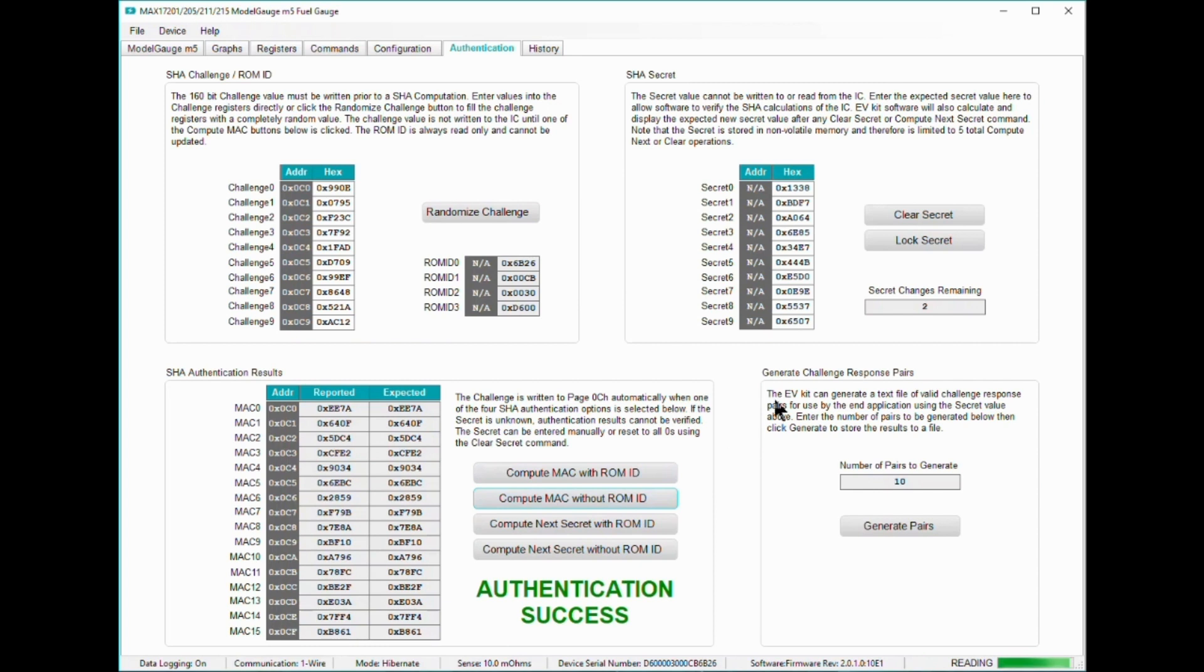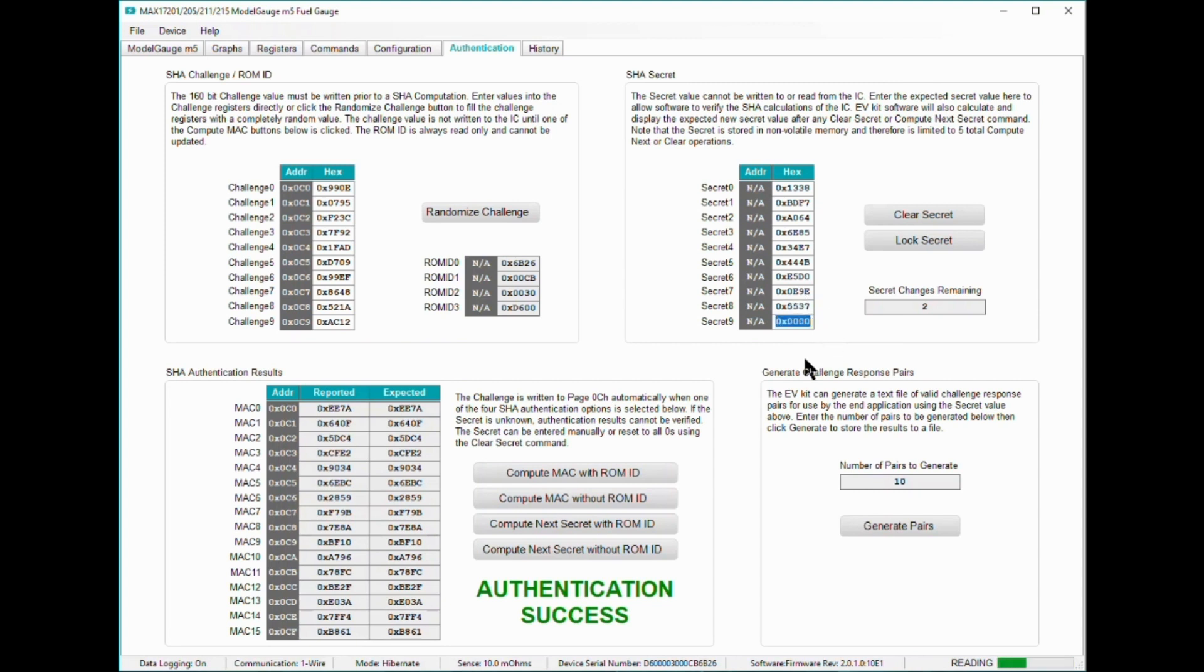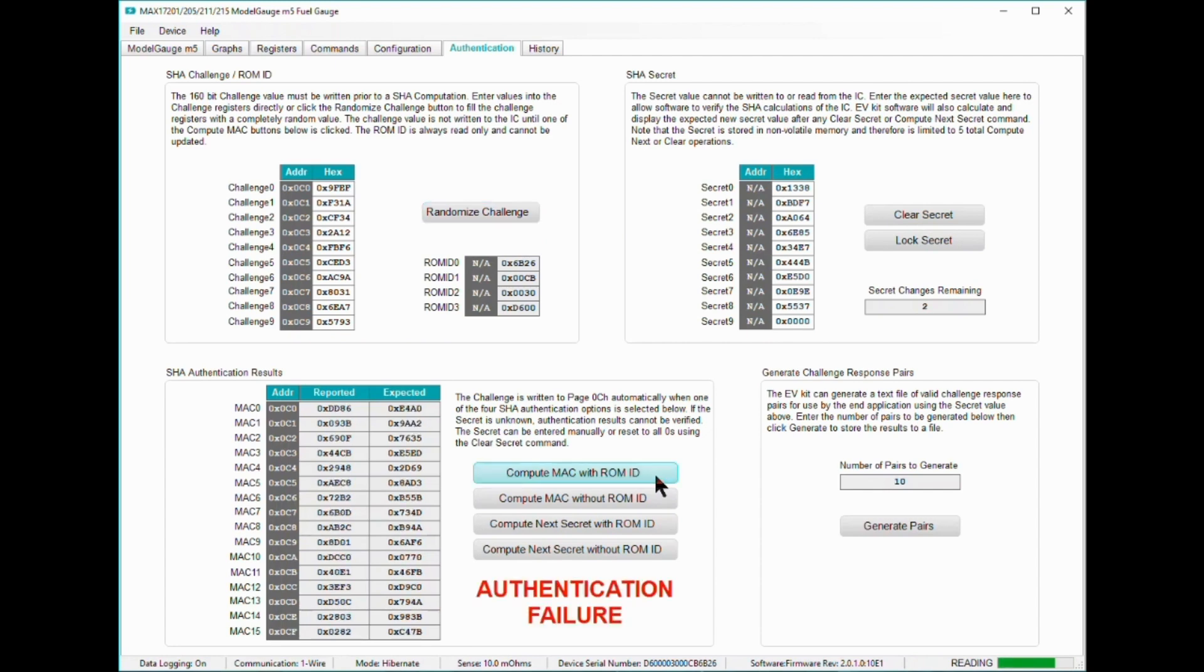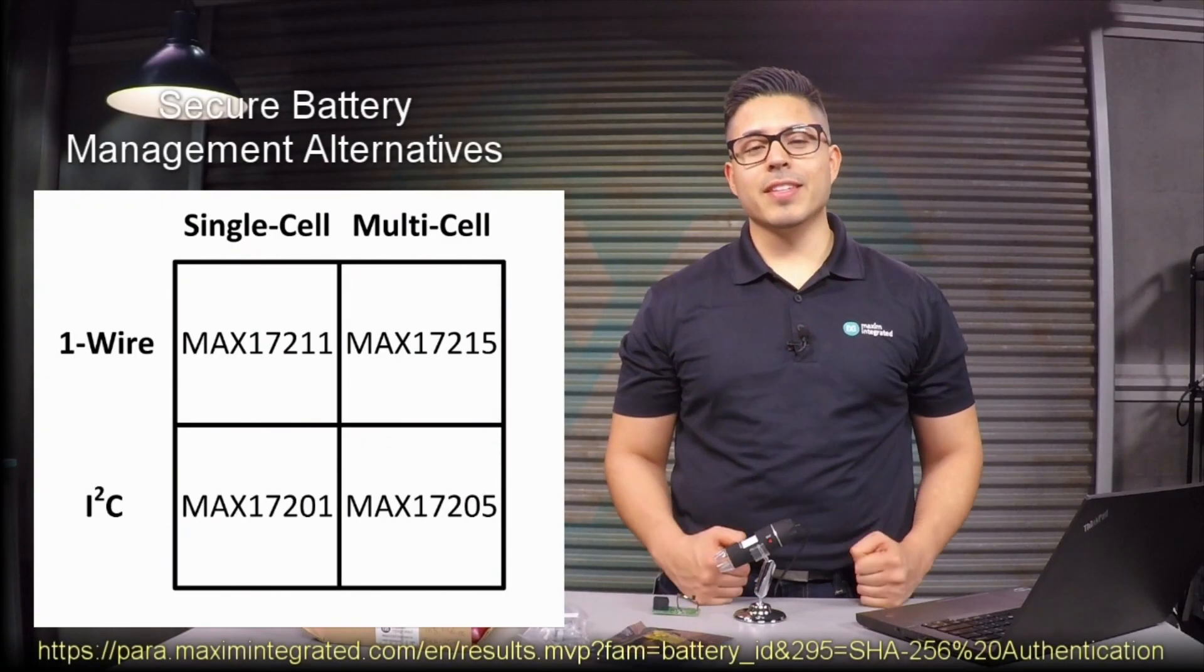In the case where a clone host does not know the secret private key of the MAX17211, a MAC that is completely different than one generated by the MAX17211 will result in authentication failure. The same logic applies if a clone battery was connected to a host instead. So there you have it.